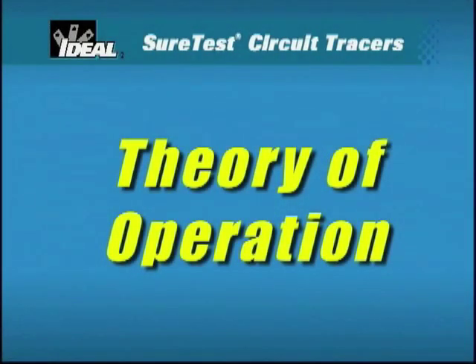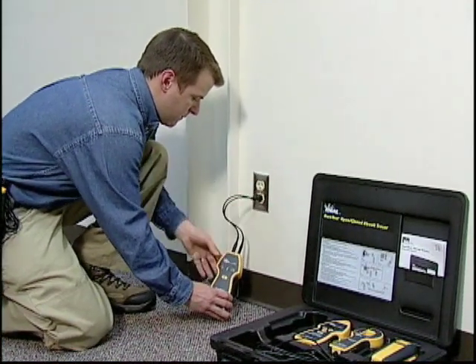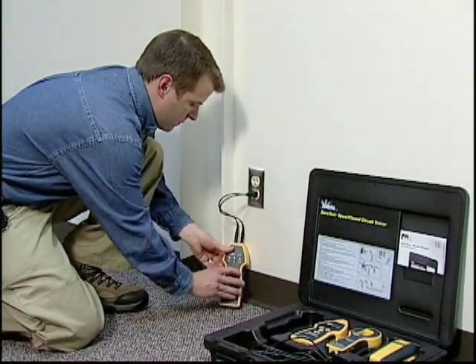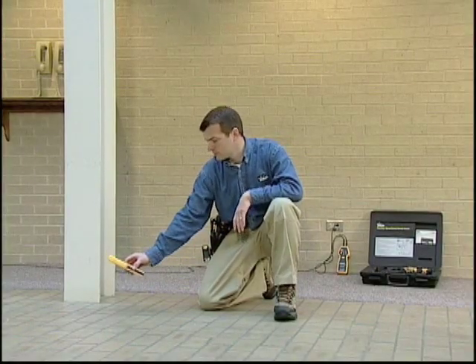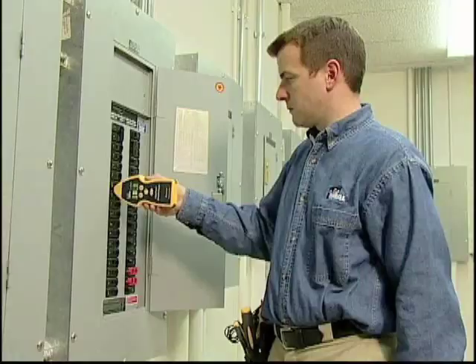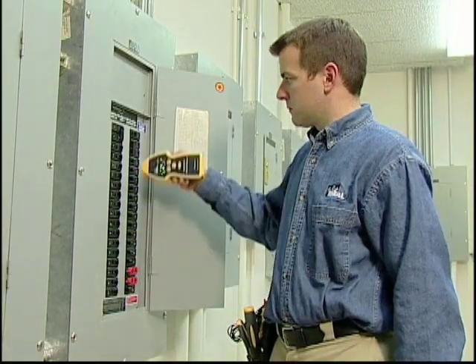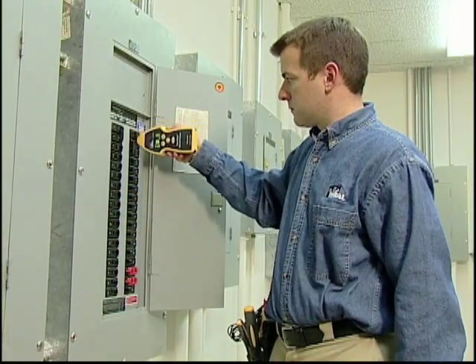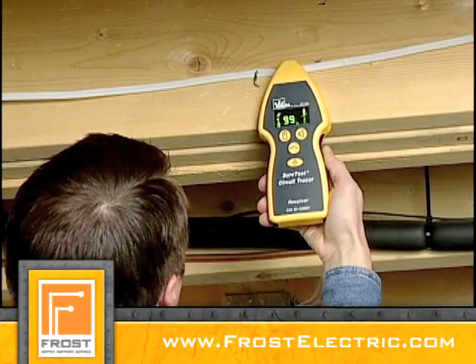It's important to understand the basic theory of circuit tracer operation. The transmitter generates a pulsed electromagnetic field onto the circuit. The receiver detects the relative strength of this field when placed in the proper orientation to the wires being traced or breakers being identified. As the signal becomes stronger, the receiver's numeric value and variable pitch and tone increase.